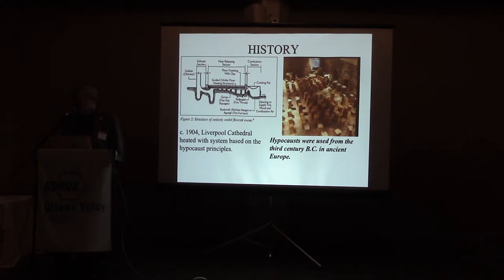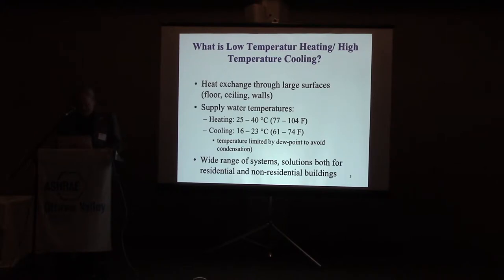New houses will have radiant floor heating. Now, why are we interested in radiant heating and cooling? It has to do with the temperature we are using for providing heating or removing heat from our buildings. So often we talk about low temperature heating and high temperature cooling, because if you use large surfaces for the heat exchange, you can go with temperatures which are getting closer to the space temperature you want.